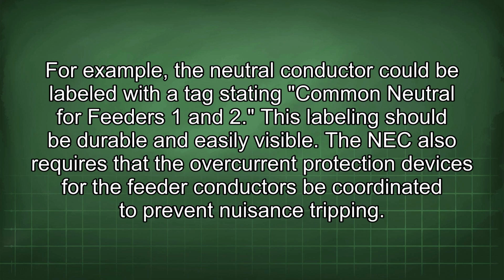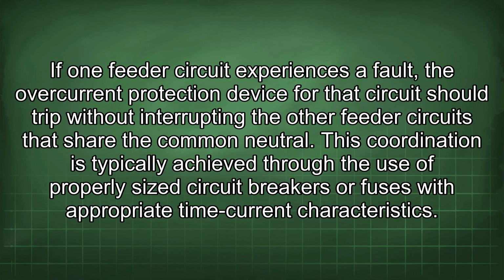The NEC also requires that the overcurrent protection devices for the feeder conductors be coordinated to prevent nuisance tripping. If one feeder circuit experiences a fault, the overcurrent protection device for that circuit should trip without interrupting the other feeder circuits that share the common neutral. This coordination is typically achieved through the use of properly sized circuit breakers or fuses with appropriate time current characteristics.